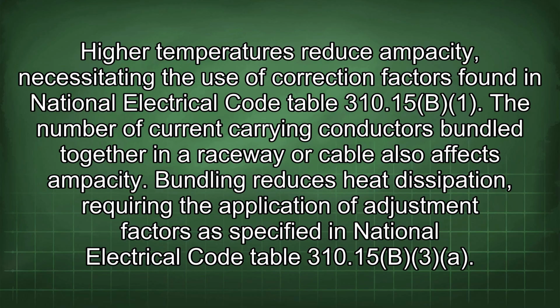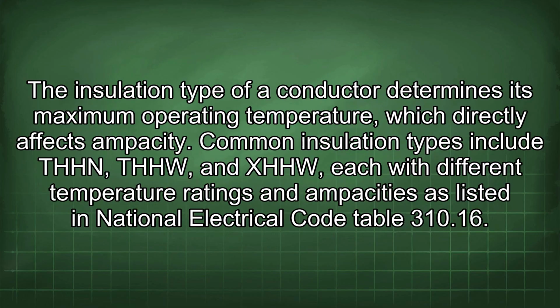The number of current-carrying conductors bundled together in a raceway or cable also affects ampacity. Bundling reduces heat dissipation, requiring the application of adjustment factors as specified in National Electrical Code Table 310.15(B)(3)(a). The insulation type of a conductor determines its maximum operating temperature, which directly affects ampacity.